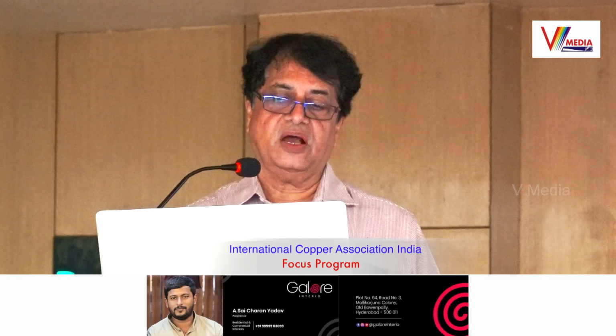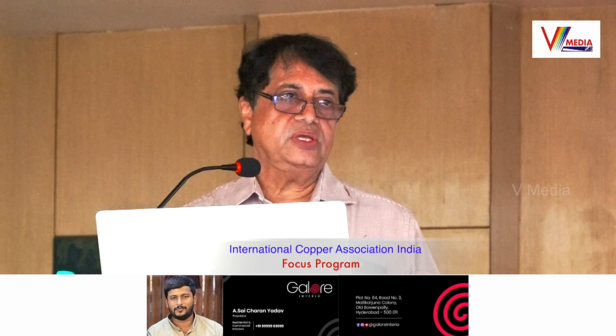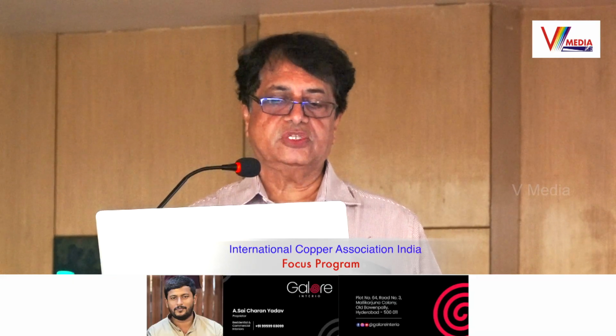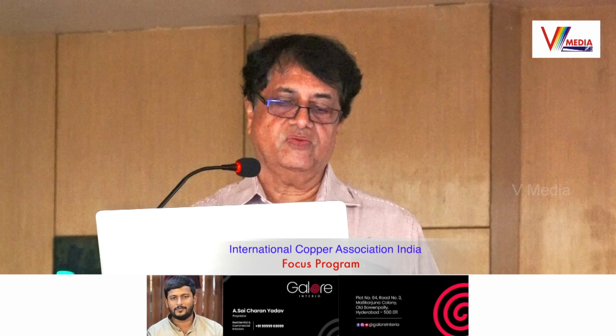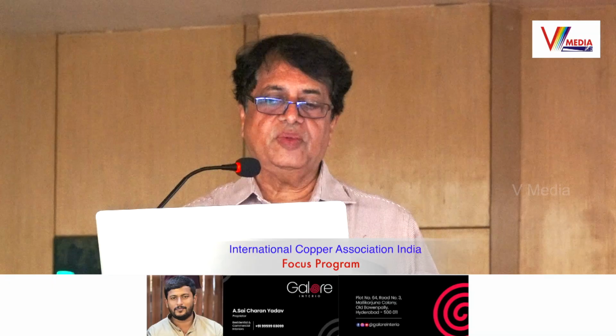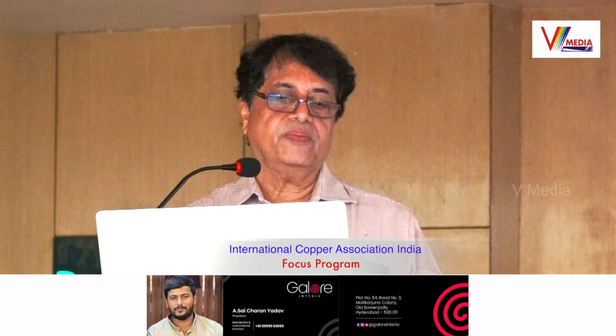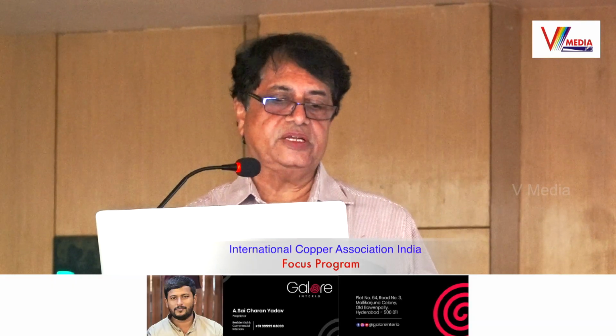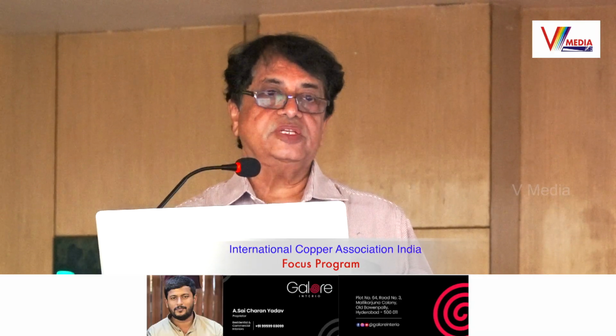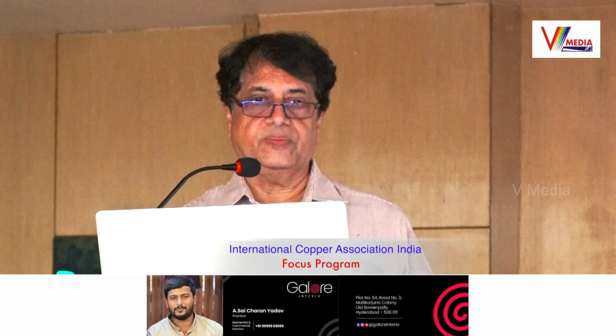Now, if you are going to use bus duct in the electrical shaft, it is natural that you may not be able to install your electrical meters at the ground floor. In that case, you will have to install electrical meters on every floor. Suppose this shaft is coming from your ground floor. This is the tap-off switch which is taken from this bus bar, and from this tap-off, a small cable connection is given to this meter box. This is the meter box. And the number of flats in the apartments, or shops, have meters installed on the same floor. Again, this point comes under the purview of the architect, that there should be sufficient space to install meters on each floor. So the design should be made in accordance with that.